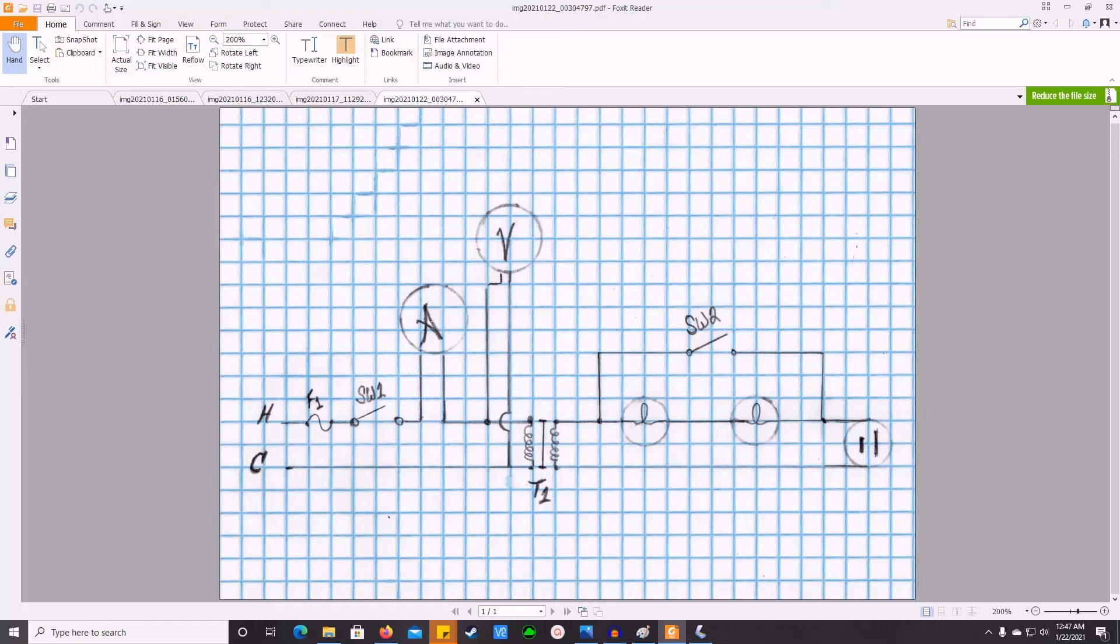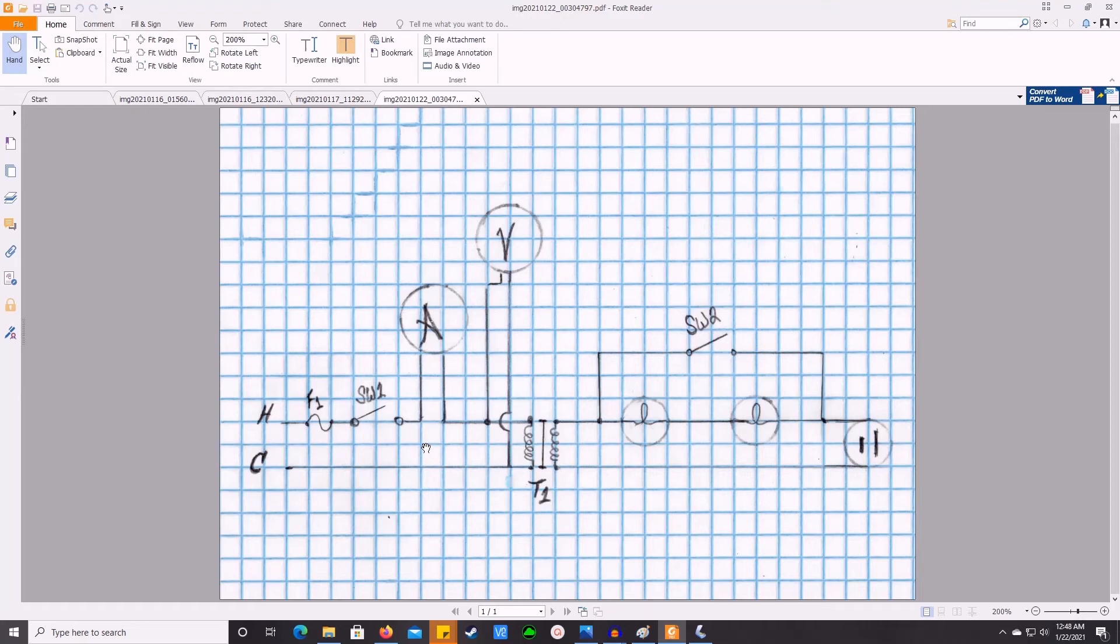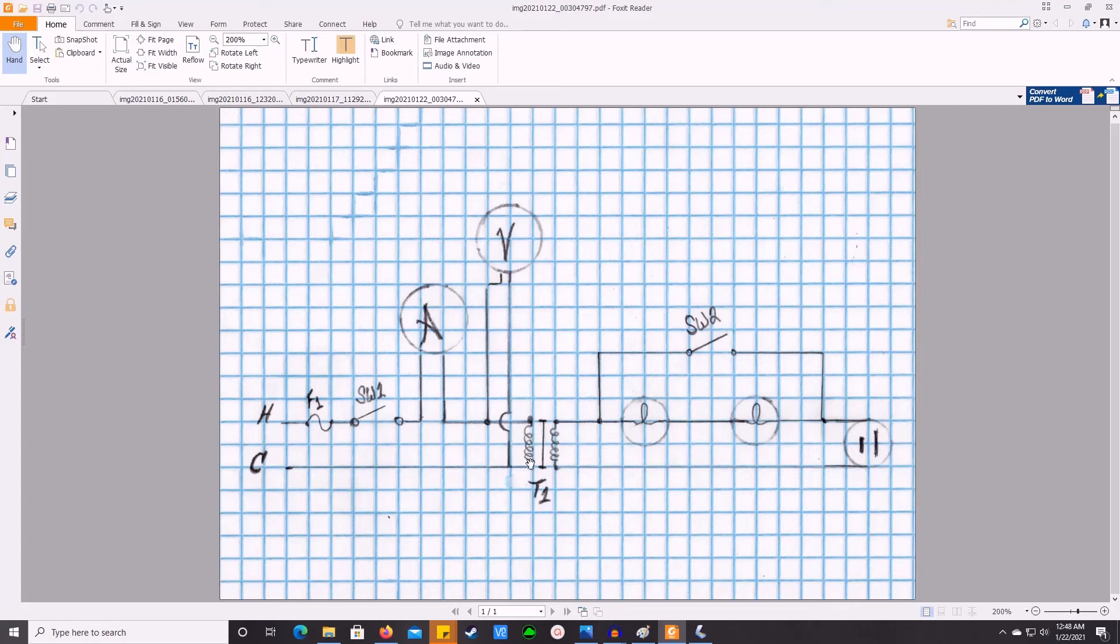So looking at our schematic from left to right, you see near the hotline you've got fuse one. That is our fuse, we physically don't have one of those yet as we're waiting for them to show up, but that will be installed when it comes in. Switch number one is going to be our on/off switch. Of course the ammeter is in series as exactly as described, so that the current will flow through the meter. And then the voltmeter is exactly like you would probe for potential across two points while you're testing for voltage. And then the last little component is the primary side of the coil on the transformer. So that's essentially that portion of the circuit.